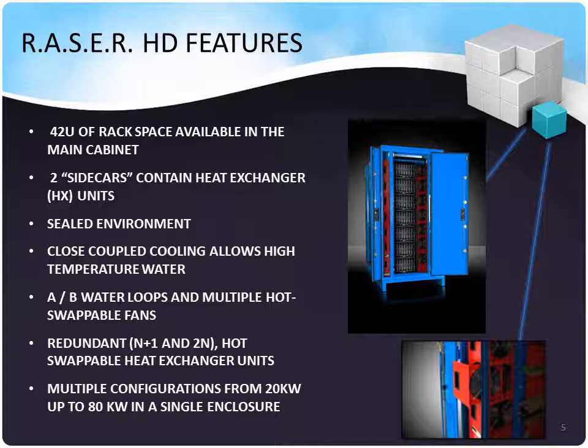Thanks, Tony. This is Simon Rorick here to talk to you about the R.A.S.E.R. HD. It has 42U of very deep rack space available in the main cabinet. On each side are two sidecars containing heat exchangers. It has a sealed environment. Closed-loop cooling allows for high-temperature water cooling strategies. Each heat exchanger has an A and B water loop and multiple hot-swappable fans to meet Tier IV data center infrastructure requirements. Each unit is redundant, so you can go N+1 or 2N, and each heat exchanger unit is hot-swappable.